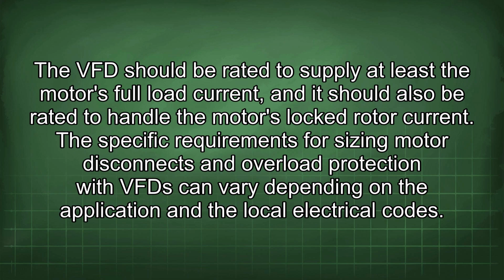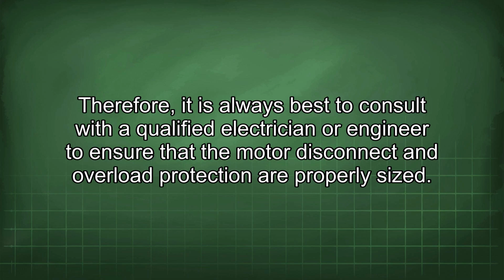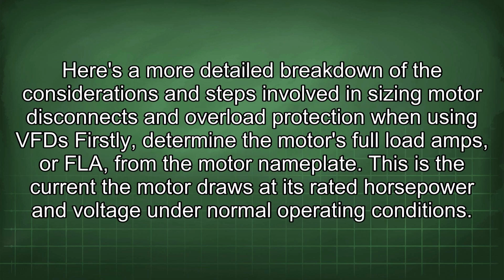The specific requirements for sizing motor disconnects and overload protection with a VFD can vary depending on the application and the local electrical codes. Therefore, it is always best to consult with a qualified electrician or engineer to ensure that the motor disconnect and overload protection are properly sized. Here's a more detailed breakdown of the considerations and steps involved in sizing motor disconnects and overload protection when using a VFD. Firstly, determine the motor's full load amps, or FLA, from the motor nameplate. This is the current the motor draws at its rated horsepower and voltage under normal operating conditions.